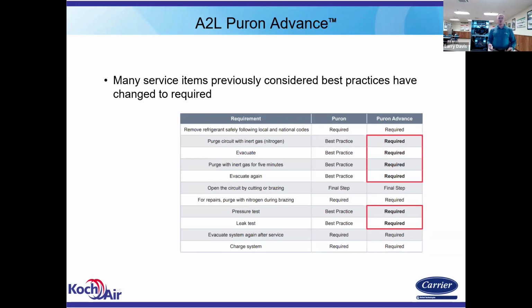So you're going to do a pressure test and a leak test. Then you're going to evacuate, and you're doing those with nitrogen. Then you're going to evacuate it, and then you're going to charge the system. Prefer to be charged as a liquid.